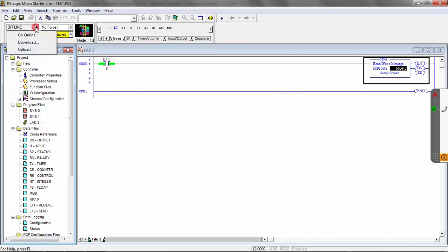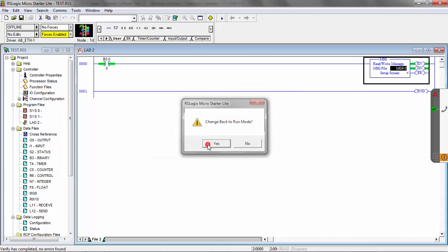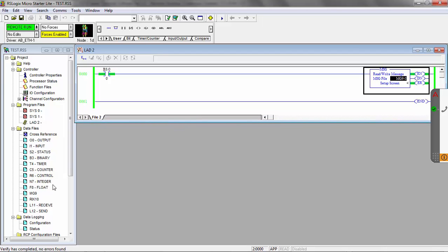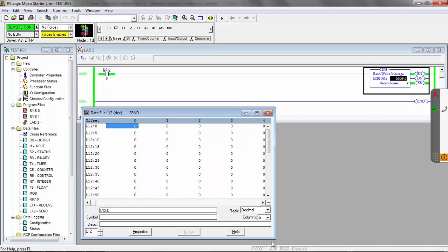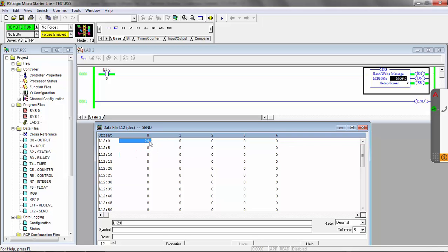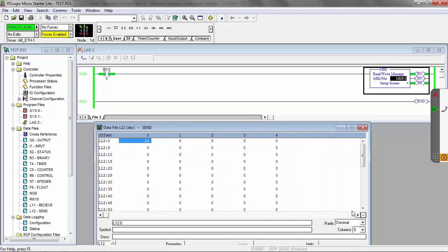I'll close that out and download this to the PLC, then test out this message. In the send information, bytes 0 and 1 need to tell it how many bytes we'll be receiving — that's six items, four bytes each, so 24 bytes. We need to load in a 24 here. If you needed to put an offset in, that would be bytes 2 and 3. Since this is a long data type, you'd need to get to the binary level. We're going to put no offset and simply receive 24 bytes.